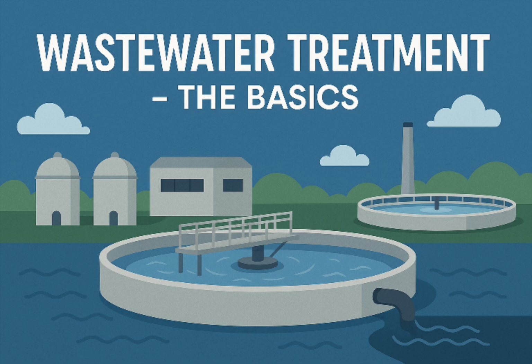And what does that achieve? It does a couple of really important things. It significantly reduces the volume of the sludge, breaks down the organic matter, and kills pathogens. Plus, it reduces odors. And I read something about biogas, a useful byproduct. Yes, that's a major benefit. Anaerobic digestion produces biogas, which is mostly methane and carbon dioxide. This biogas is combustible, so it can be captured and used as fuel, often to heat the digesters themselves or even generate electricity for the plant.